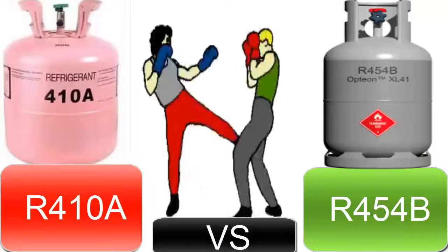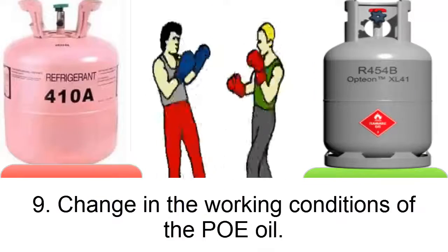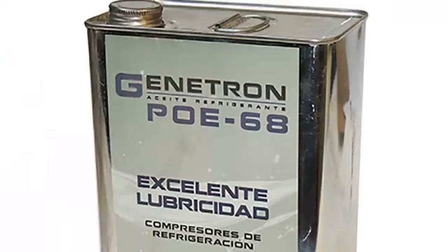9. The oil selected for the compressor with R454B considers a higher discharge temperature compared to the discharge temperature of R410A, which can influence the compressor's performance under certain conditions.